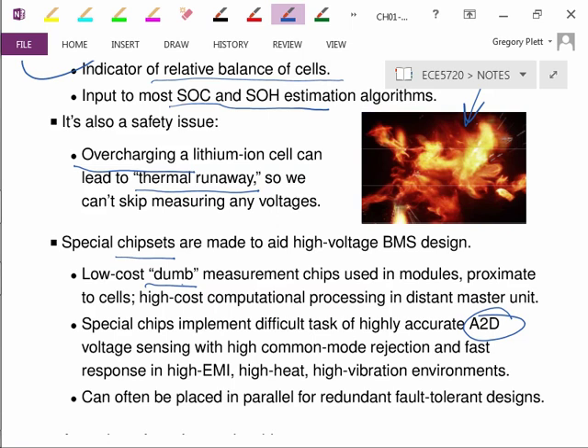That's not always true. Sometimes there are wires from every cell going back to the master unit, and these measurement chips are not proximate to the cell, but proximate to the master unit instead. That introduces some concerns with noise injection with long wires that you have to be concerned about, but it's a design issue - what are the trade-offs, and how do you really want to do it?